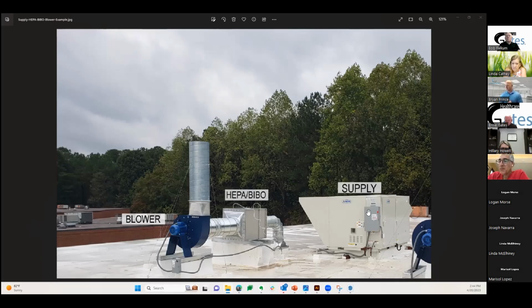This newer technology is called digital scroll, or modulating, or simply dual compressors. That means temperature and humidity are independent variables, read independently of each other. This computerized piece of equipment, which I told you costs $50,000, decides how it's going to handle a temperature set point and a humidity set point.